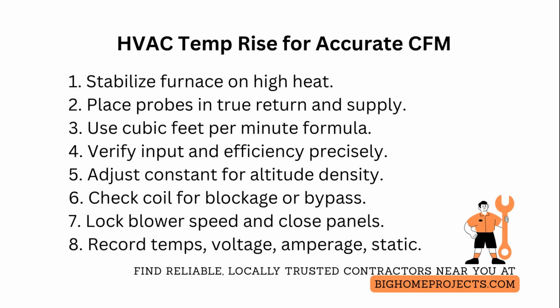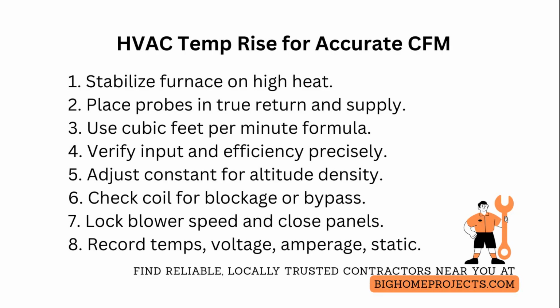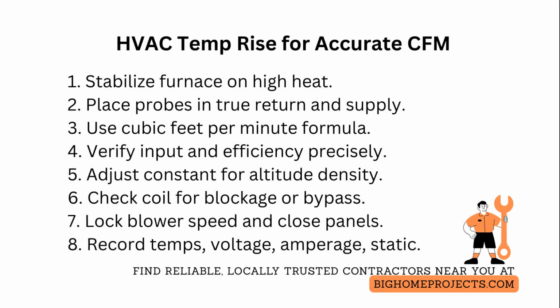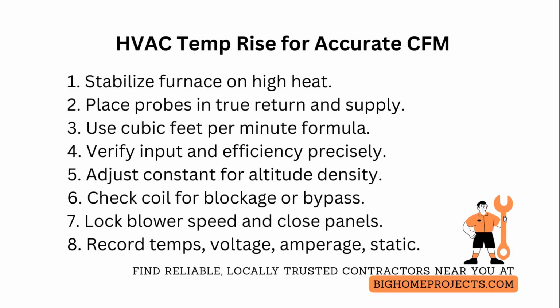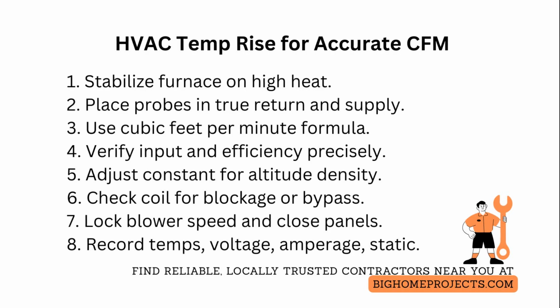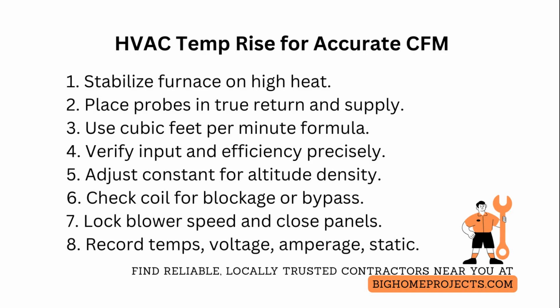Place your temperature probes upstream of the heat exchanger in true return air, away from the burner vestibule, and downstream in the main supply trunk after the coil but before any branches, so you capture the real temperature rise that matches the furnace rating.